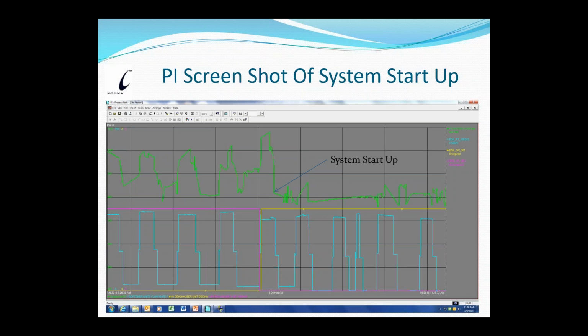Yes. He wanted to know what the y-axis on the PI screenshot was, and that was gallons per minute. And I used different scales. The green is 400 to 1,100 gallons a minute. The blue was 0 to 400 gallons a minute. And then the next two are just which softener is running at the time, so it's either 0 or 1. So I could show that it wouldn't fill up the whole screen, I made it 0 to 2, but it's actually a 0 to 1 number.